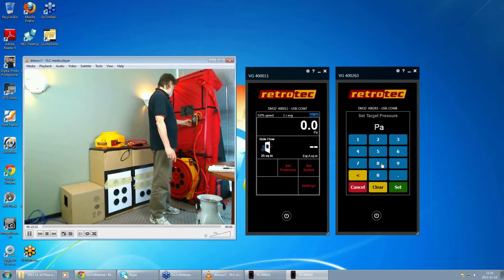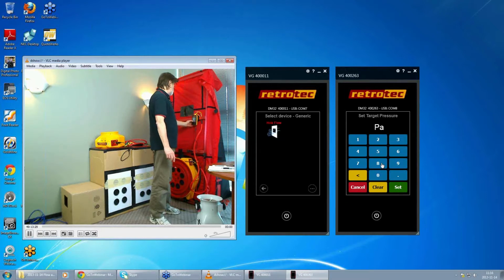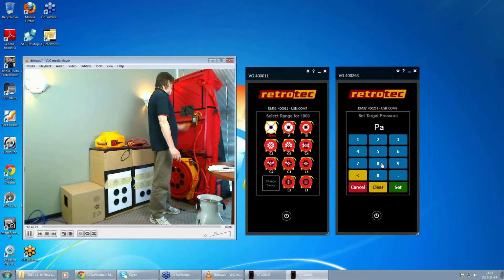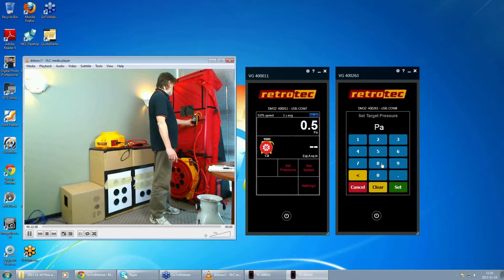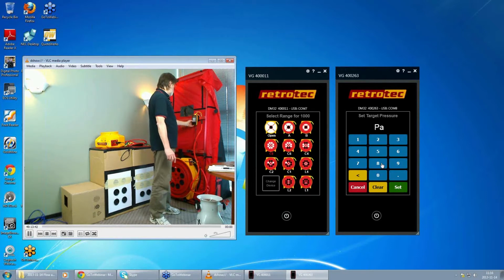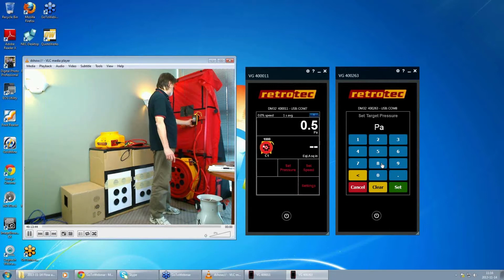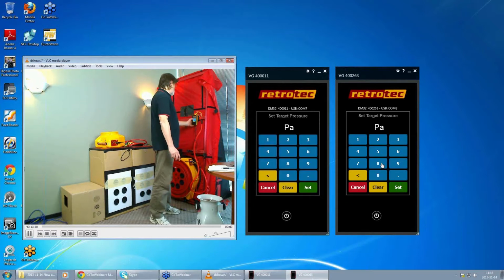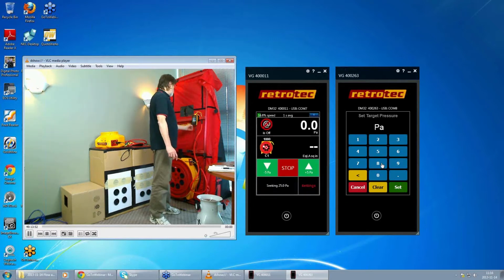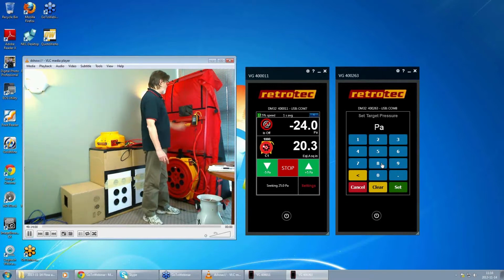So we're going to set the pressure, just change that to the device that I'm on here, which is the 1000 fan. The range I'm on is C1, which is that one there. Okay, so I'm on the right range, and so now I want to set pressure to 25, enter. So we've set the pressure to 25 pascals.